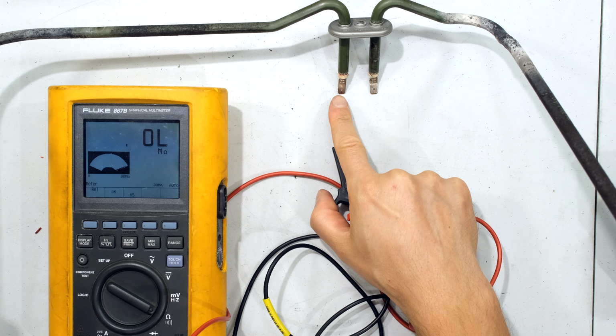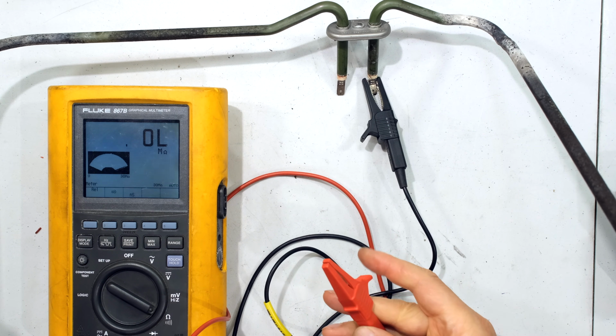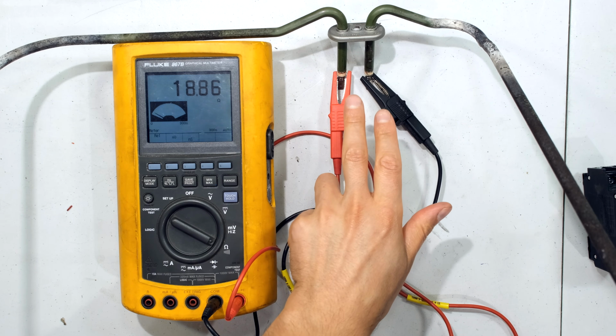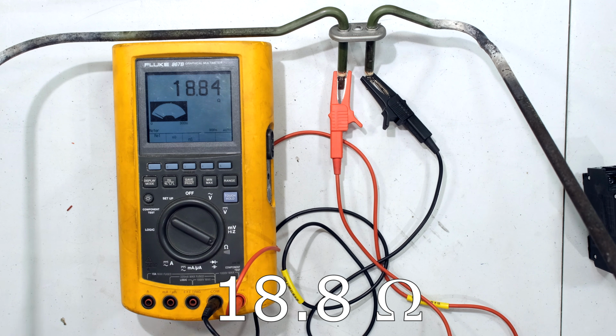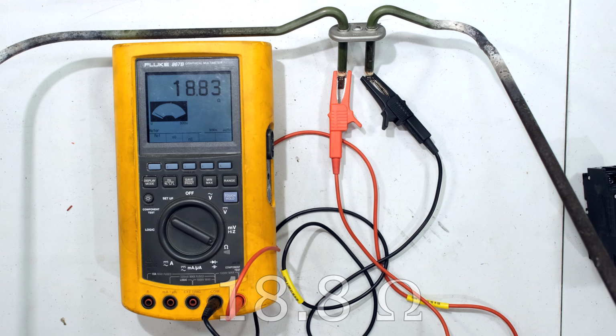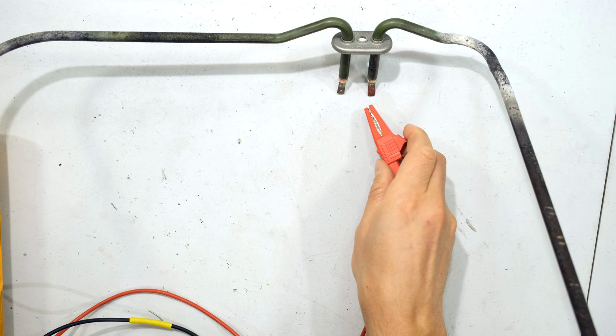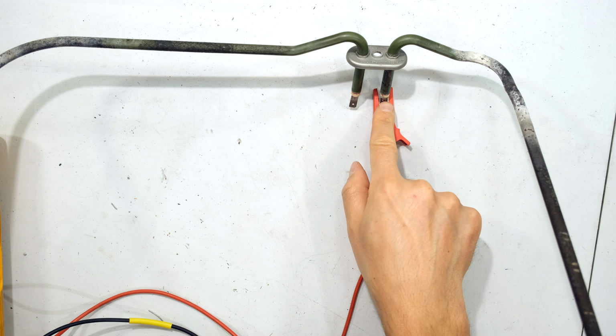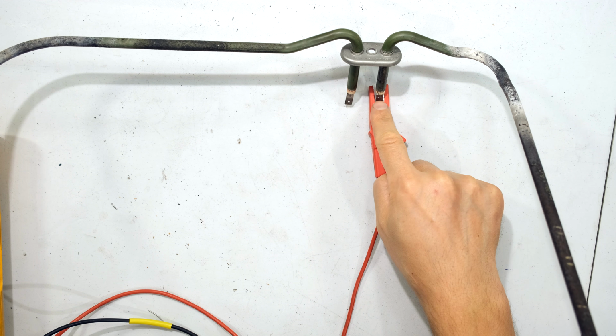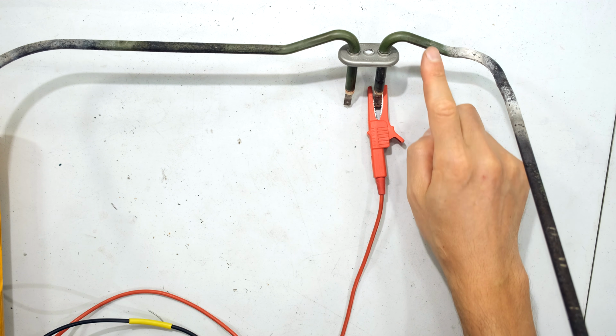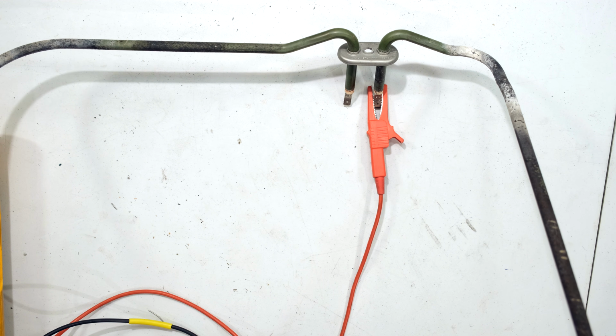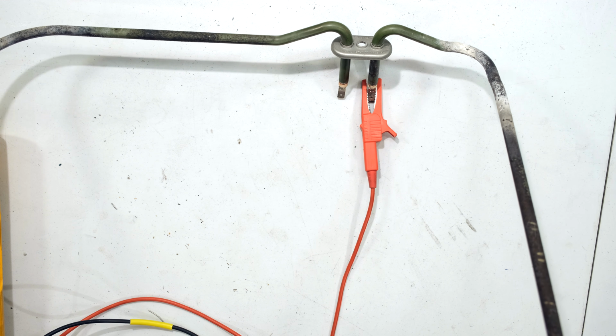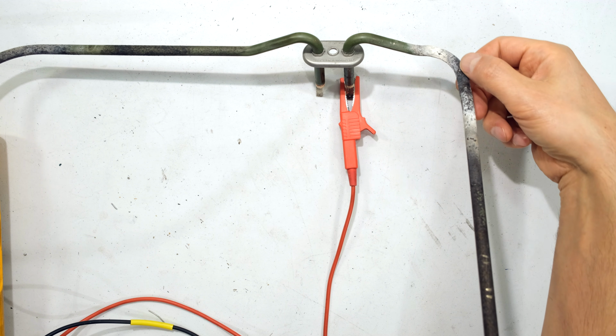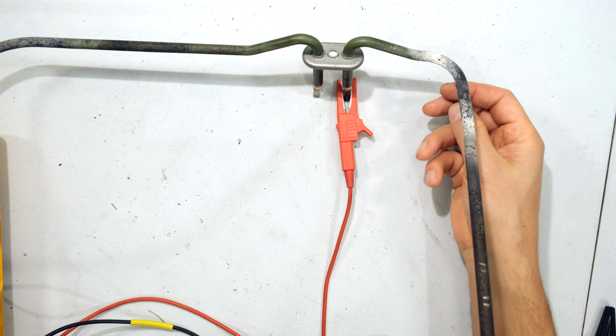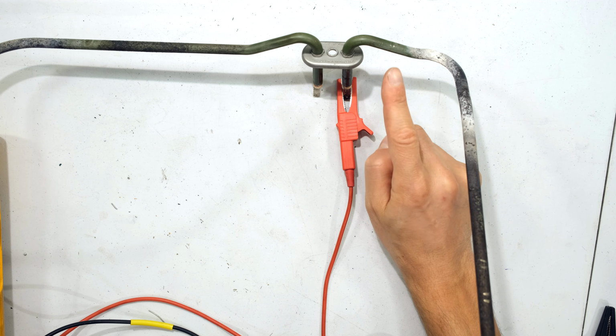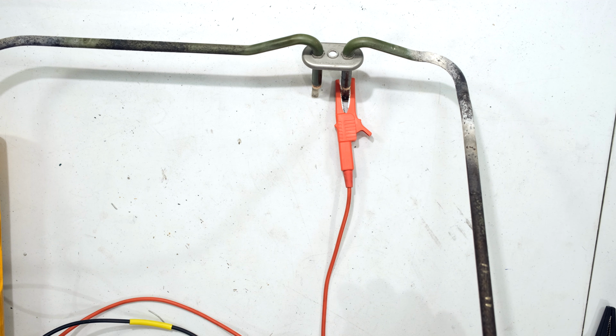Right, so what I'm going to do is first measure the resistance between the terminals. This is the element, the nichrome wire or whatever wire is inside here that gets hot, and you can see there it's less than 19 ohms, telling me that that is fine. Now I'm going to put my multimeter clamp over there, and measure the resistance between that and the casing. Now this casing is steel and it heats up and cools down many times, and because this is in water, sometimes we get moisture inside here, we get an insulation breakdown, and we find that the resistance between there and here reduces. Now why is that a problem?